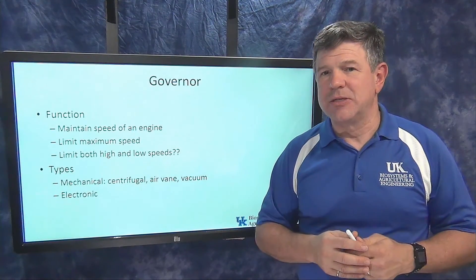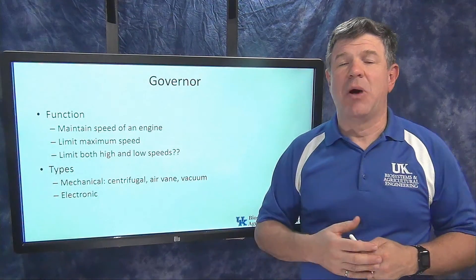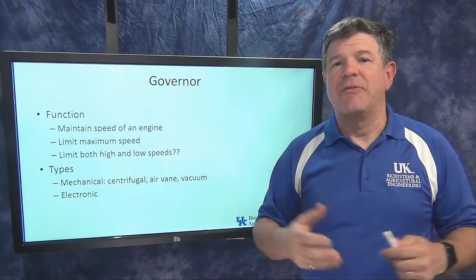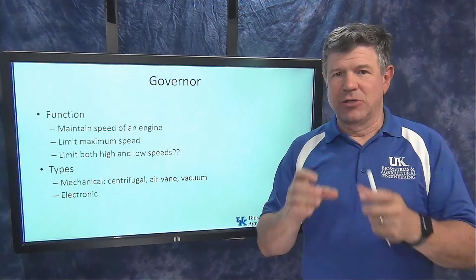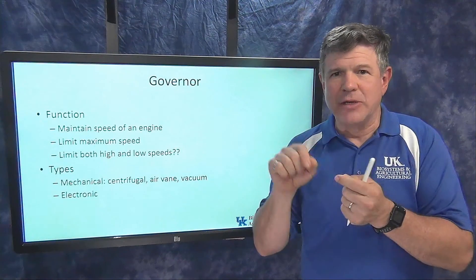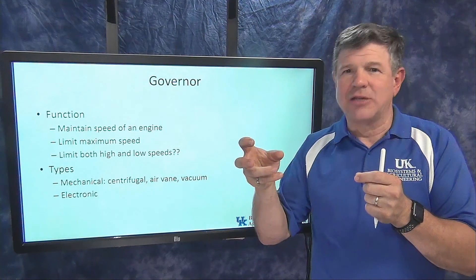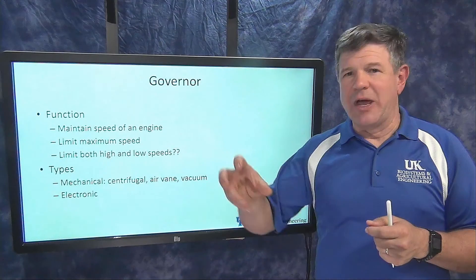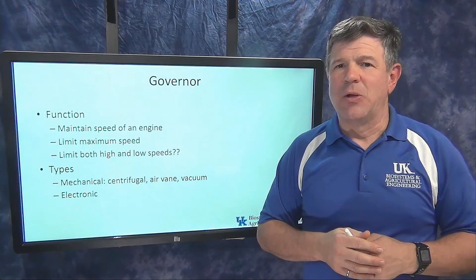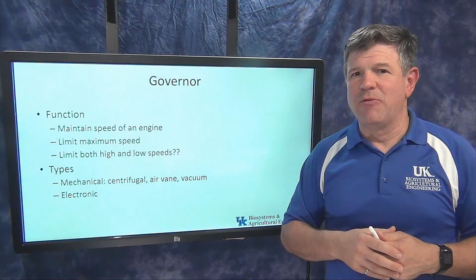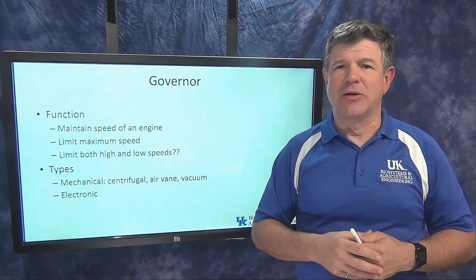On older large engines, they will have mechanical type governors. But many newer engines, even some newer small engines, will have electronic governor systems. These use an electronic sensor to measure speed, feed the signal into a small computer, which decides whether the engine is too fast or too slow, then sends a signal to an electronic actuator that opens and closes the throttle plate or adjusts the injector pump to get more or less fuel into the engine. That's governors — a summary of what we looked at and talked about, and hopefully this helps us understand how they work.